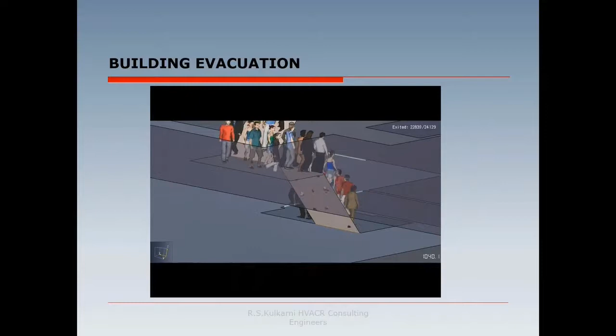Question from Ashu Vyas: what is the positive pressure ventilation prescribed by many fire officers in certain regions for stairwell pressurization? Okay. The recommended pressure inside the lift well or stairwell is from 12 Pascal to 90 Pascal. Now, why there is a pressure range is that when we start any VFD or fan, since it is a mechanical component, it needs certain time to get adjusted. So this is the recommended pressure range from 12 Pascal to 90 Pascal.